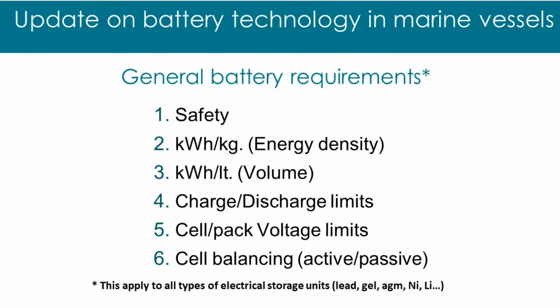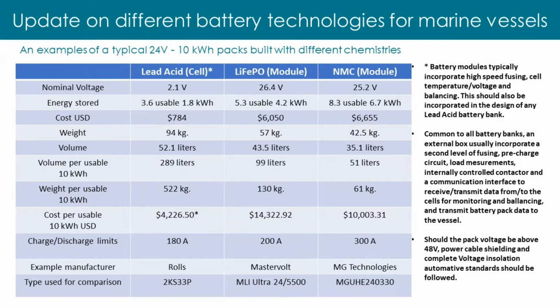Number four is the charge and discharge limits, which relates to safety. If you over-discharge a battery or discharge it too fast, it might heat up, and in the case of lead acid batteries, could start boiling and lead to catastrophic damage. The same applies to lithium cells, any technology — shorting the cell or the pack can have very negative consequences. That's why, on top of monitoring voltage and temperature, it's important to monitor the charge and discharge rate. This applies to all battery chemistries — make sure the charge and discharge limits stay within what the manufacturer specifies, since these are specific to each chemistry.